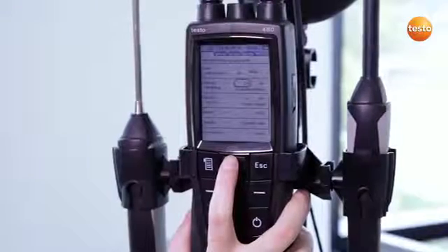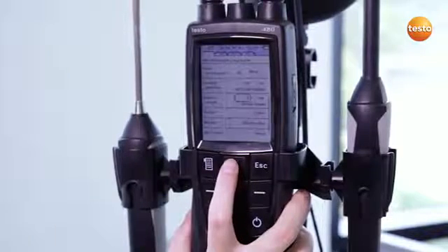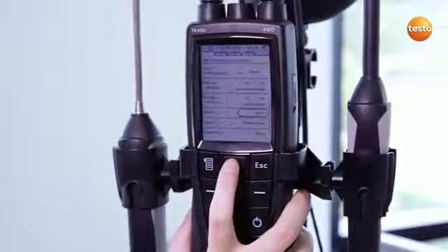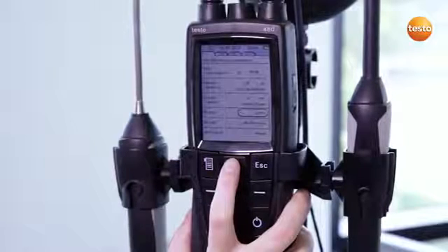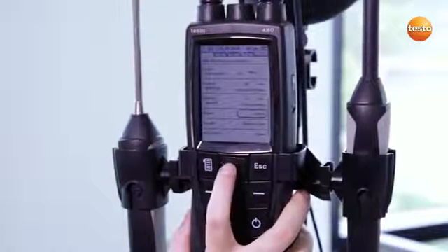The Testo 480 has its own measurement program, which guides me step by step through the settings. In addition to the measured parameters, I need to input information on the type of clothing and the degree of activity of the staff. For example, at 22 degrees centigrade, light summer clothing and a seated office job lead to a perception of the temperature as too low.